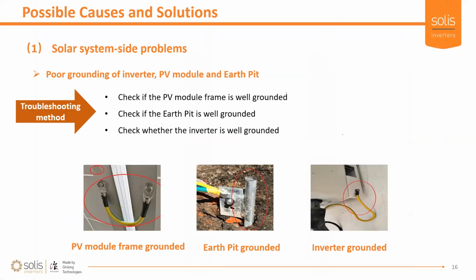This is still an issue with the installation side. Earthing your PV side doesn't really help remove this issue. It's actually just a safe thing to do. You don't want floating conductors in your installation, so just make sure that you're earthing all your conducting items in your installation. However, the earth to the inverter is very important for this. If your earth to your inverter is floating, your detection circuit doesn't have a solid reference to compare with, and you will get nuisance tripping. You could get nuisance tripping, or you could get fail-to-detect results, which would cause the inverter to start generating into this fault and make everybody very, very sad.